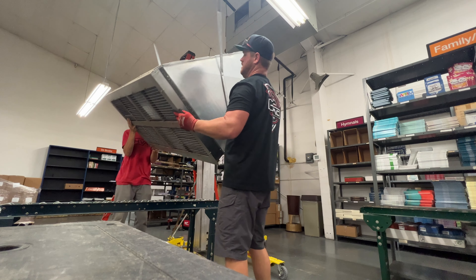I don't really trust that one lift alone is going to keep the unit nice and level as we go up. I wanted to go ahead and reconnect the duct down here first so it's easier to install and seal, and once we get it up in the air it's done. So I decided to mount a come-along up on that beam so it can support one side while the lift supports the other side. We've got our rubber clamps and all-thread — everything's ready to go.